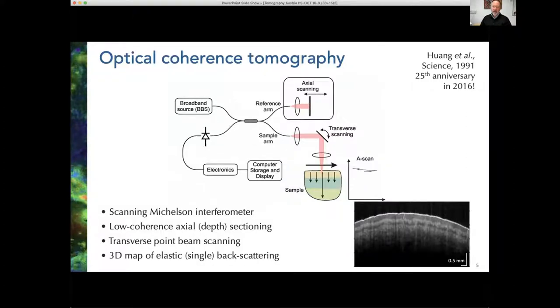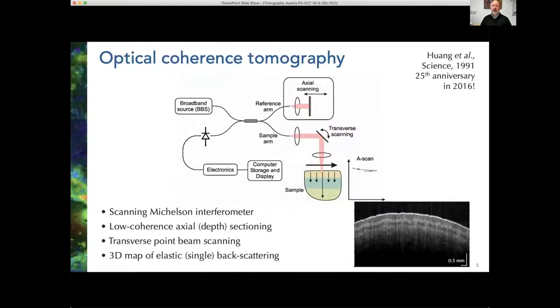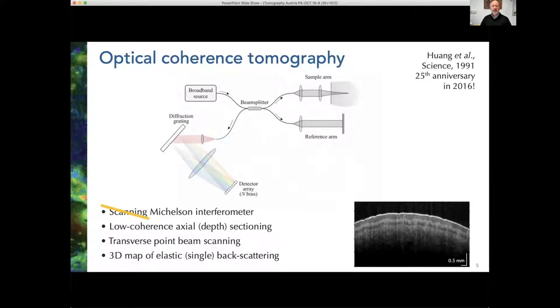OCT has had its 25th anniversary already in 2016, which means it's up for its 30th anniversary. Time is flying. In essence, we're talking about a scanning method which generates two-dimensional or three-dimensional images by scanning a focused beam in two dimensions, and in the third dimension producing depth sectioning through optical interferometry. Key to that is the use of a broadband light source with lots of frequency components. In practice these days it's done in the optical frequency domain with a spectrometer.